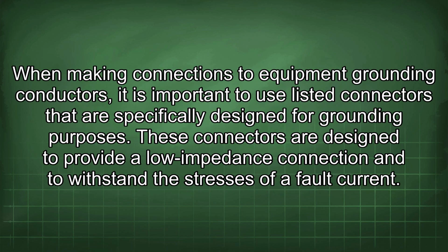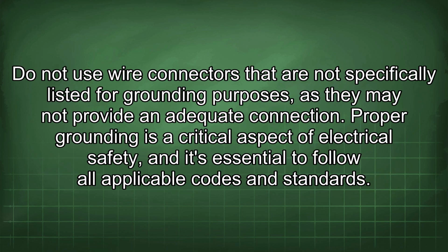When making connections to equipment grounding conductors, it is important to use listed connectors that are specifically designed for grounding purposes. These connectors are designed to provide a low impedance connection and to withstand stresses of a fault current. Do not use wire connectors that are not specifically listed for grounding purposes, as they may not provide an adequate connection.